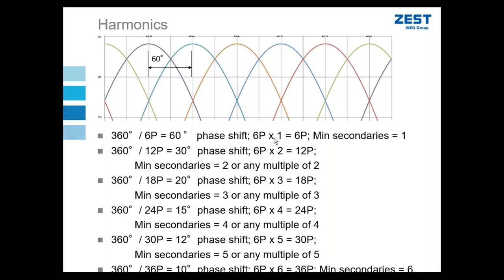My phase shift here, there is no phase shift. So I say six pulse times one is equal to 6 pulses. The minimum number of secondaries I need on a transformer, well, I don't need any, I need only one. If I go to the 12 pulse scenario, 360 degrees divided by 12 is equal to 30 degrees. I now have a 30 degree peak to peak phase angle. I need at least two 6 pulse rectifiers, as we've already seen, to give me my 12 pulses. That means I need at least two secondaries on my phase shifting transformer, or any multiple of two. So I can have 4 secondary windings, for example, on a 12 pulse rectifier.